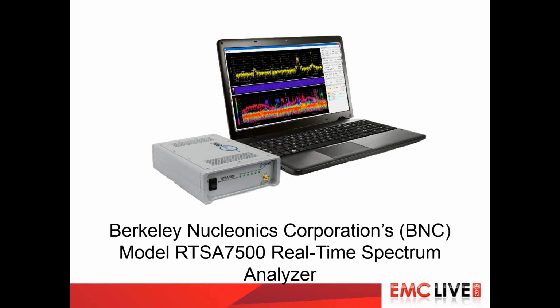Berkeley Nucleonics, which I love their BNC initials, offers a real-time spectrum analyzer, which is extremely cost-effective. This particular analyzer starts at 100 kilohertz, and in 3 different models goes to 8, 18, or 27 gigahertz. The 8 gigahertz version is $4,000. The 27 gigahertz is $13,400. It comes with software that connects to this module. You're looking at the entire system right here. There are no large analyzers you need to lug around for doing 18 or 27 gigahertz measurements. This is great for everything from Wi-Fi to cellular, telephone, or high frequency harmonics of transmitters if you have to get up in the high gigahertz range.